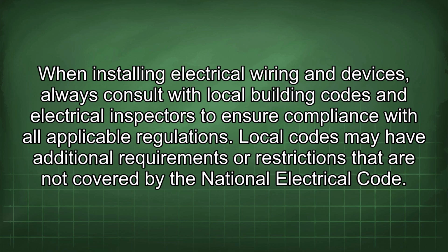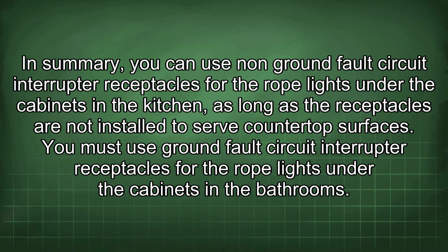When installing electrical wiring and devices, always consult with local building codes and electrical inspectors to ensure compliance with all applicable regulations. Local codes may have additional requirements or restrictions that are not covered by the National Electrical Code. In summary, you can use non-ground fault circuit interrupter receptacles for the rope lights under the cabinets in the kitchen, as long as the receptacles are not installed to serve countertop surfaces.